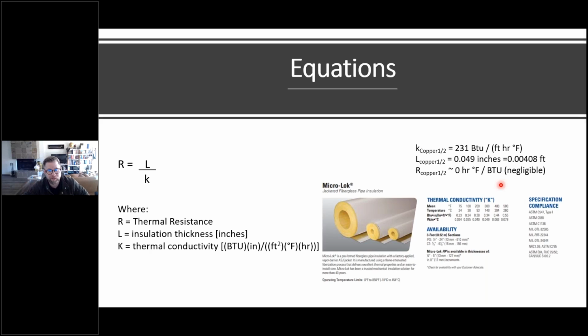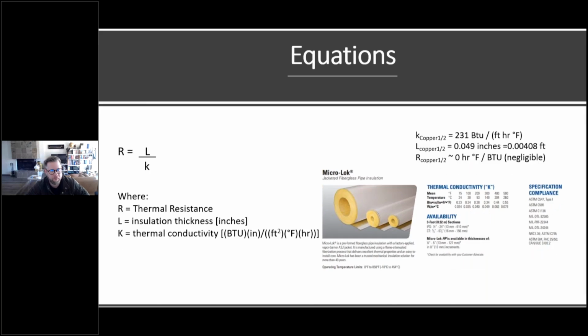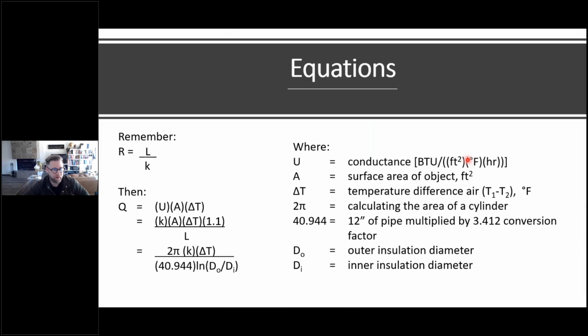If you're using other materials, it may be worth going through the calculation and adding that resistance, the resistance of the pipe material, to the insulation thermal resistance. Now, when we plug in the next step of this, so our thermal resistance, R equals L over K, it could also be determined as conductance, so conductivity being one of the types of heat transfer.